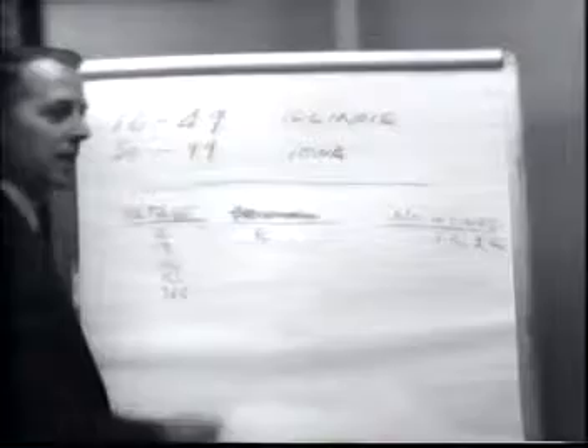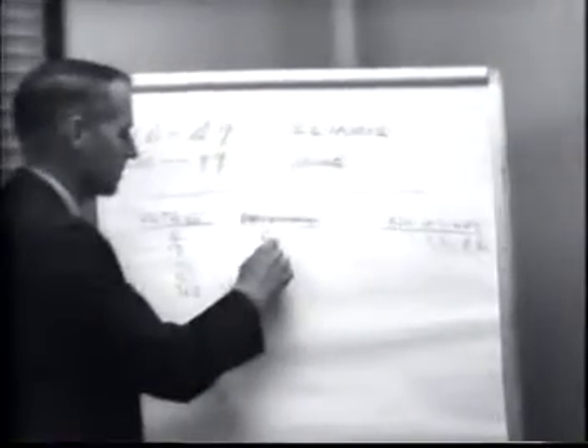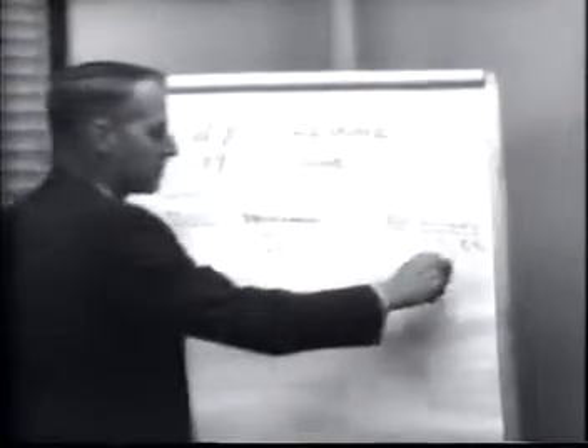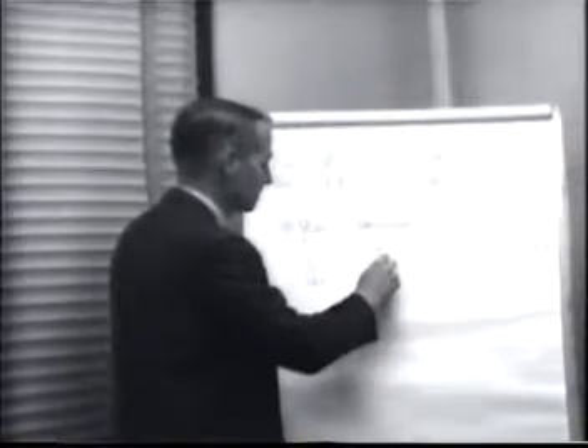Now, if we have a line that goes between two lettered substations, the letters are arranged in alphabetical order. That is, we would have a 13 kV line from sub A to sub T. This would be AT. This would be 1 or 2, and so forth. If we have a line between a numbered sub and a lettered sub, the number is given first. As for instance, we would have a line, let's see, between, say, sub 56 and sub G. That would be circuit 66, 56, G, 1.